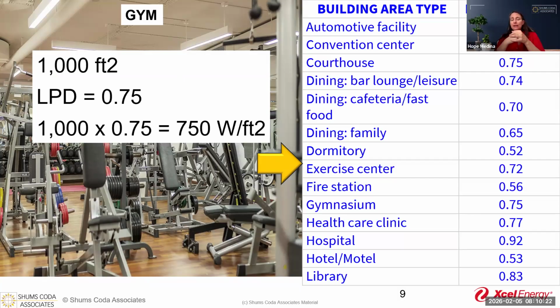And even though it says 750 watts is available for that space, it would actually be 720 because you're only allowed 0.72. My apologies for my fingers not hitting it right, but that's the concept of how this would work. So on a set of plans, I should see something like this provided, or documentation that demonstrates this concept. And we'll talk about that in just a moment.